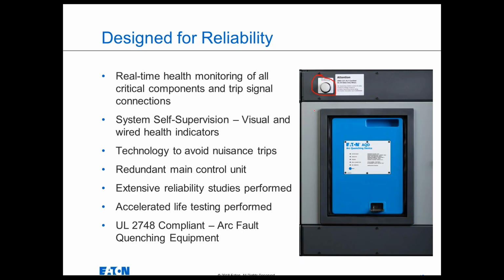The Arc Quenching device itself has redundant main control units. If one fails, the other one will pick up and it'll still operate. We've performed extensive reliability studies on all of the equipment. It's been tested and designed to the same standards that govern motor protection relays, transformer protection relays, that sort of thing. And it's actually shown to be just as reliable.